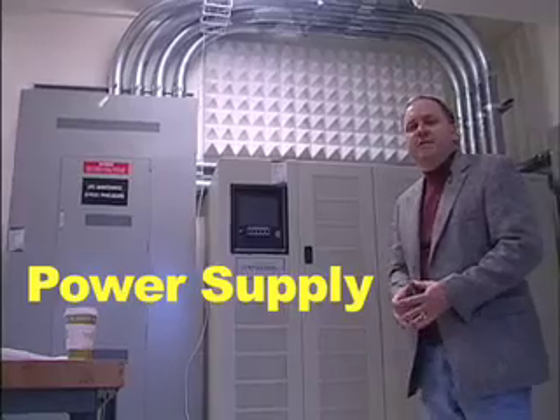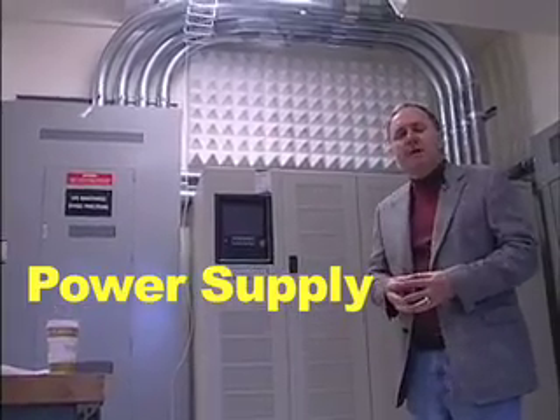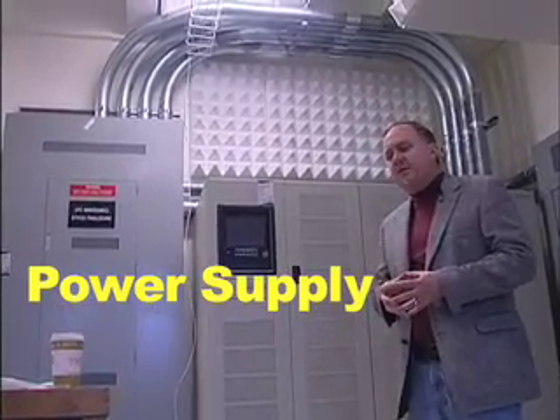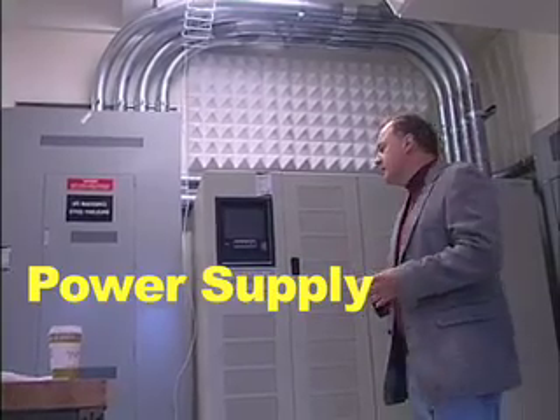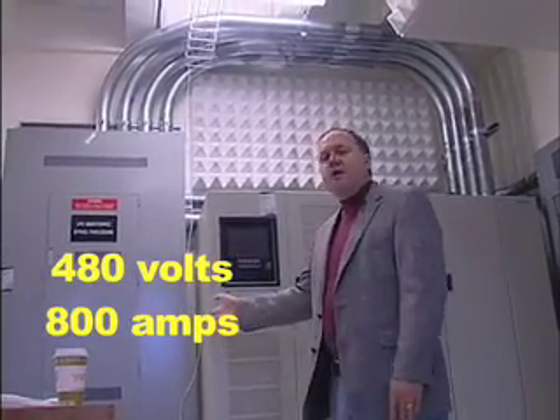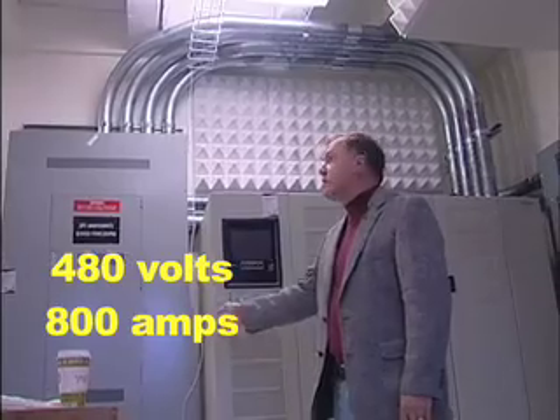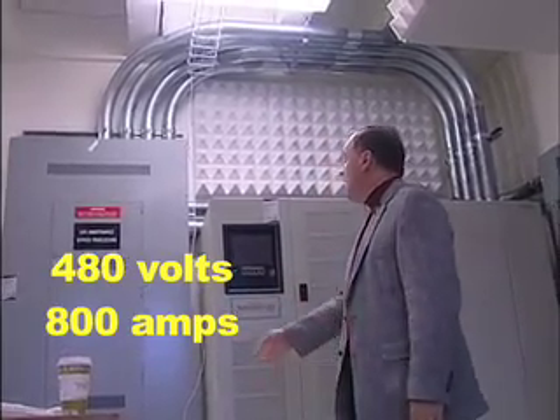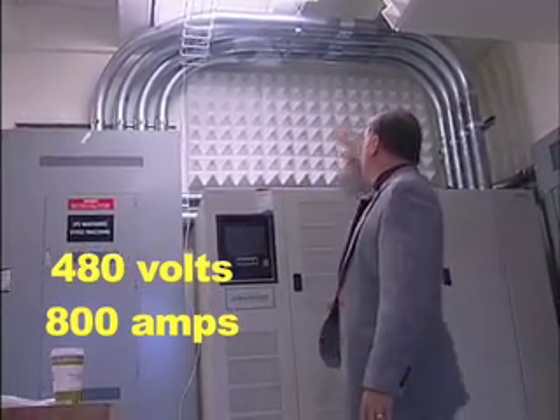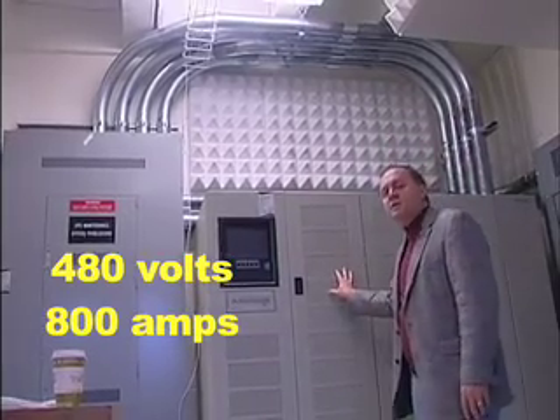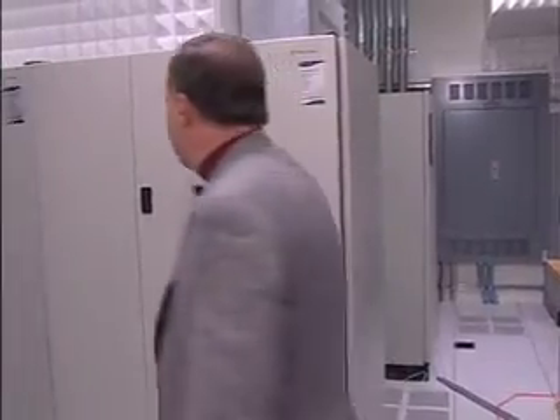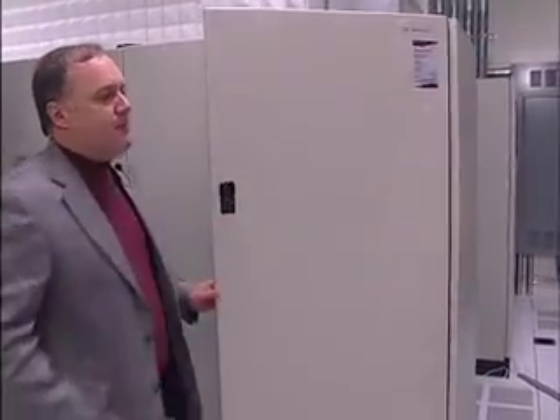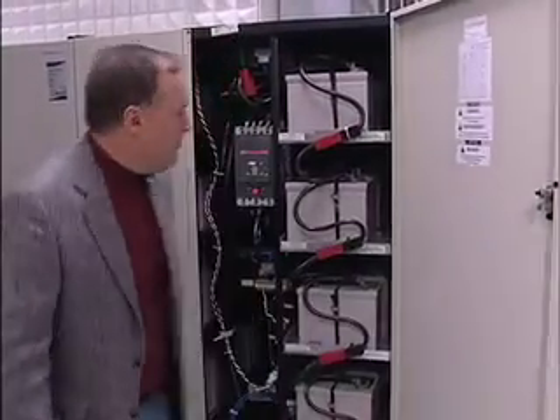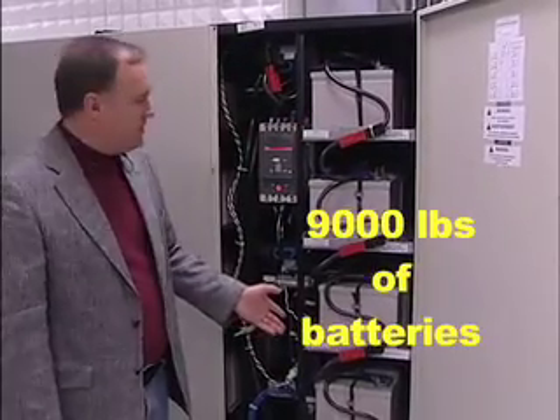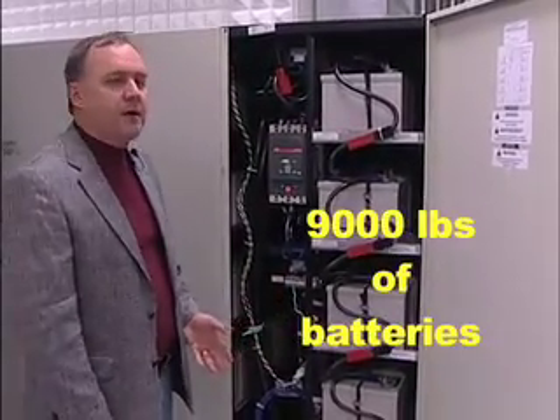As you can imagine, 780 computers use quite a bit of electric power, so we actually have a very significant power supply coming into the room. We bring in 480 volts three-phase at about 800 amps, comes into the building, from the basement into here, and this is an uninterruptible power supply, which means we actually do have battery power to run the computers for a few minutes in case power fails. And these are powered by about 9,000 pounds of effectively car batteries here.